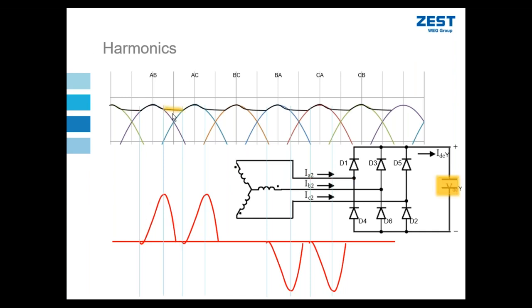The reason it drops off is that during this interval shown in orange, my load, which could be a motor on the output of my VSD, not shown in the drawing, we're just showing up to the capacitor, but imagine this VSD is connected to a motor, my motor needs to draw current. During this interval, it is now drawing its current not from phase A from the supply, but in fact from the capacitor. And that's why, if I'm examining my current at the input, I have no current drawn during that interval. Then when my capacitor voltage drops and my phase-to-phase voltage again exceeds my capacitor voltage, I'm drawing energy from the supply, and so I get another spike, another peak. And so I keep going. Then I enter another interval where my capacitor voltage is higher, and so I'm drawing current from the capacitor, not from the supply.